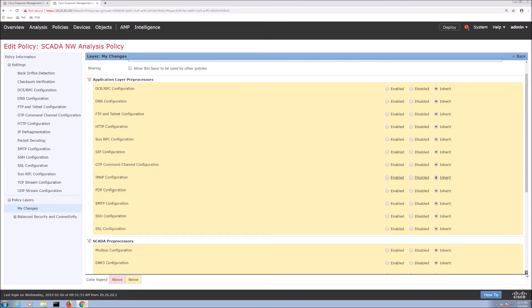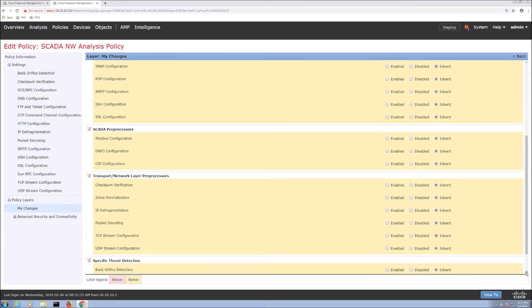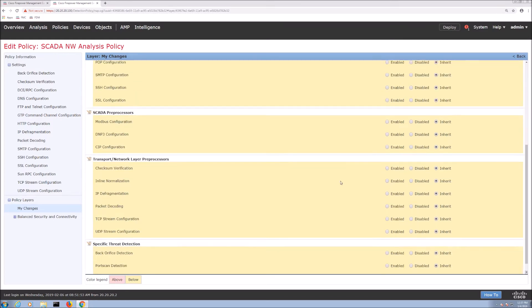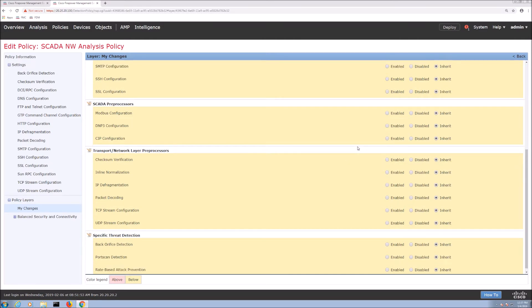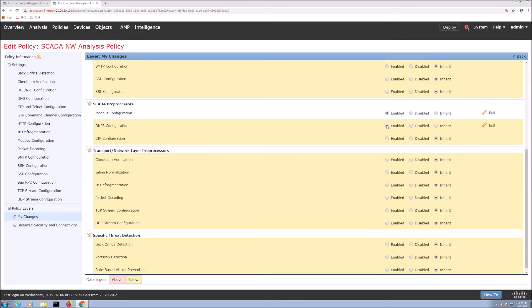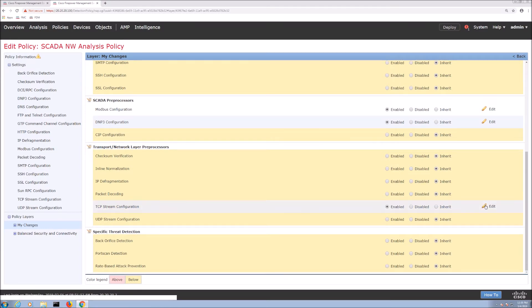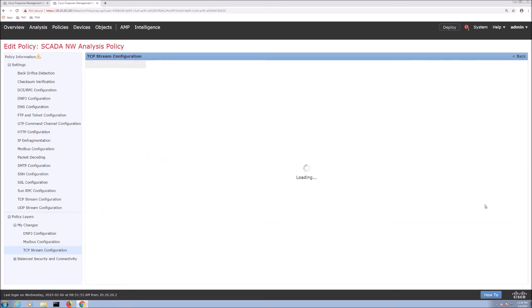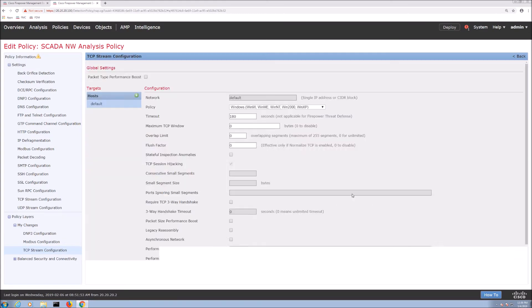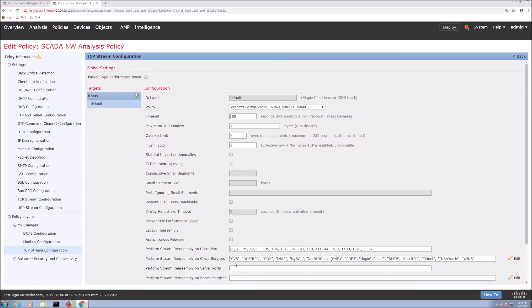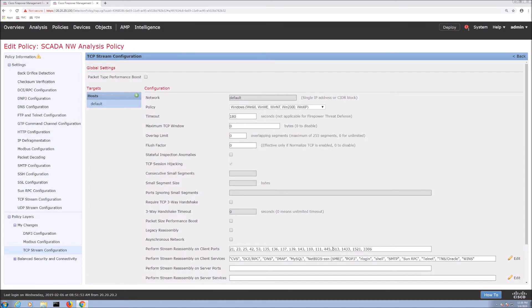And we're also going to do inline normalization for TCP stream configuration. So we are going to enable that one as well and we're going to edit that one to add in the actual ports that are leveraged by Modbus and DNP3 and so those ports are for Modbus it's 502 and for DNP3 it's going to be 20000 and I'm just putting them in order here of what you would see them in typically if they were done in order. Doesn't have to be but that's what I'm doing anyway.